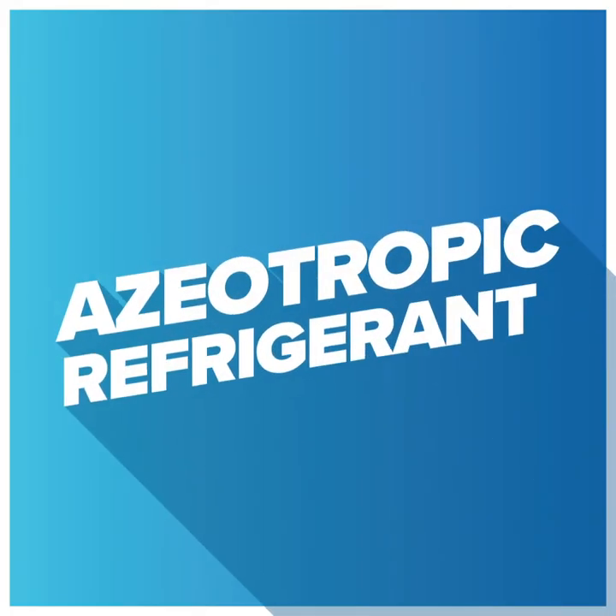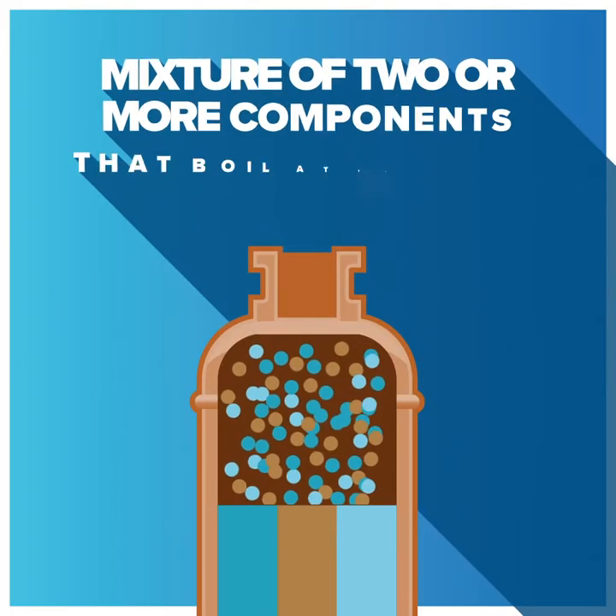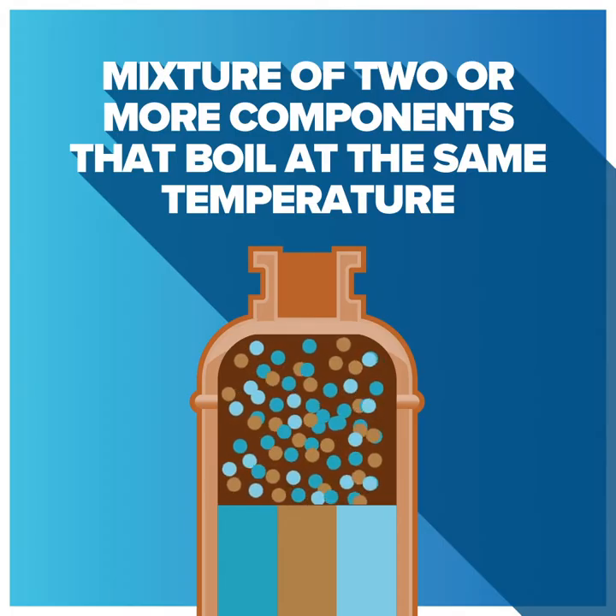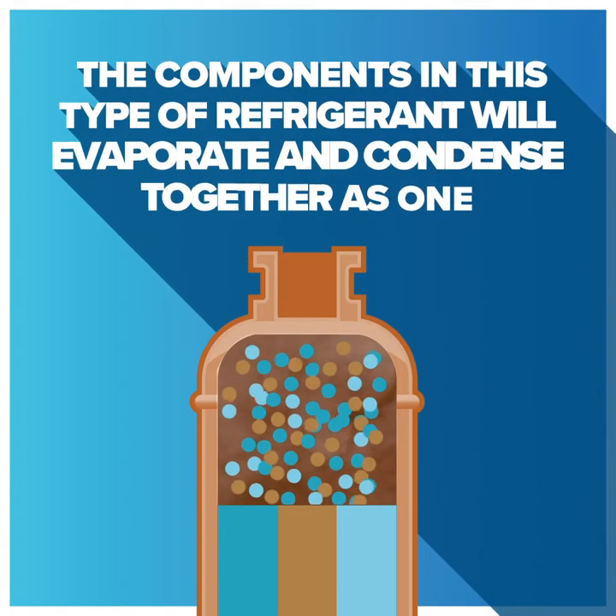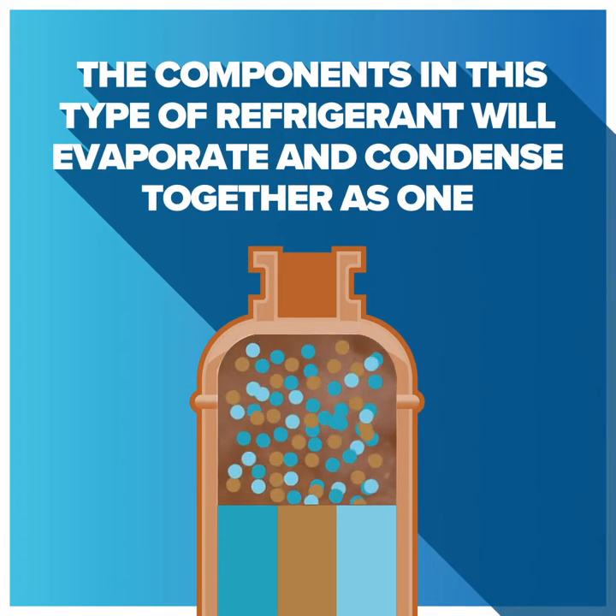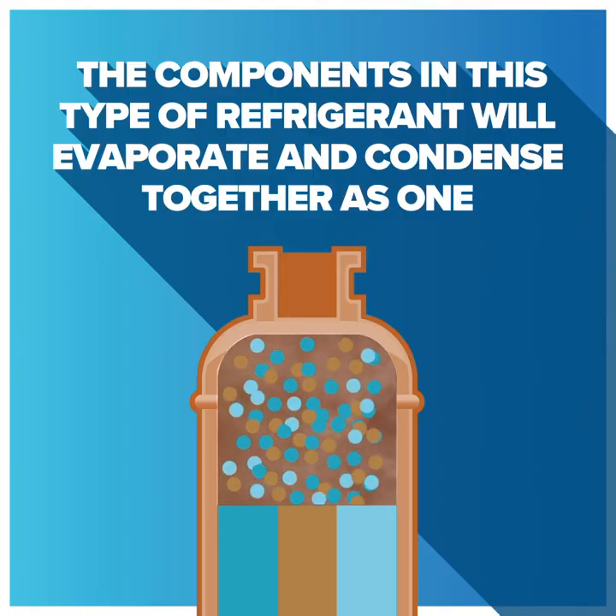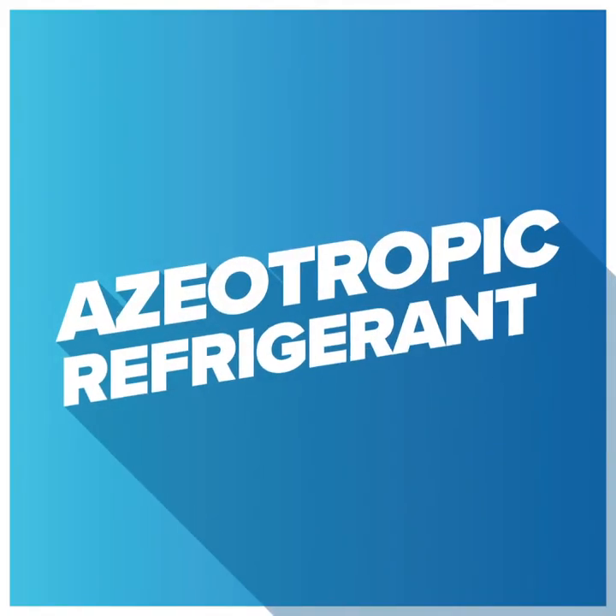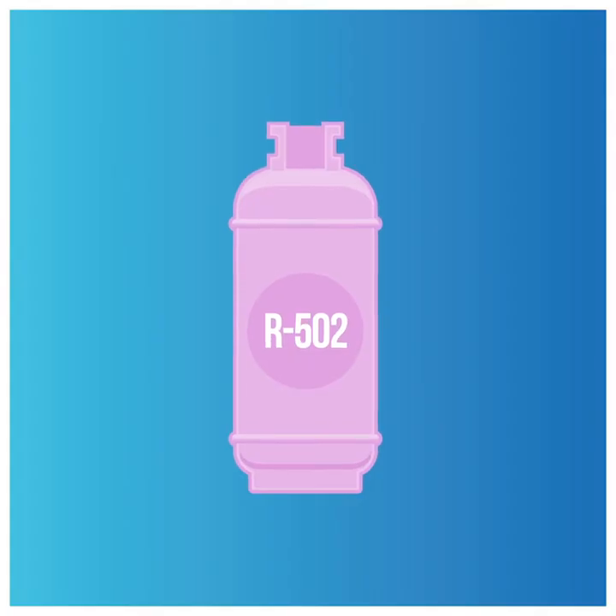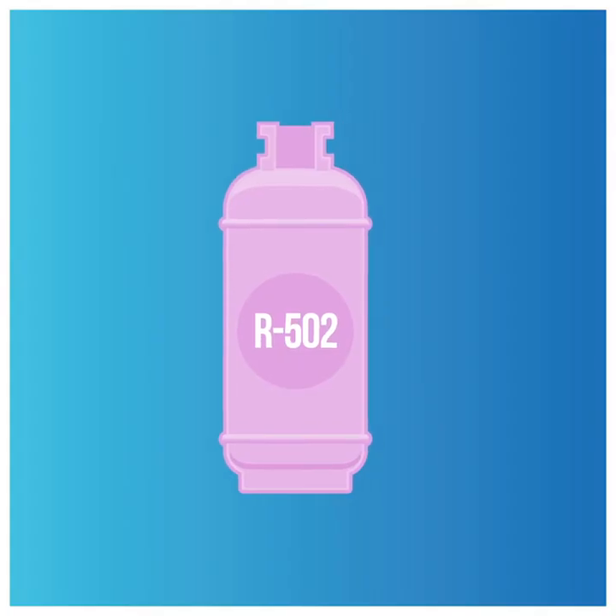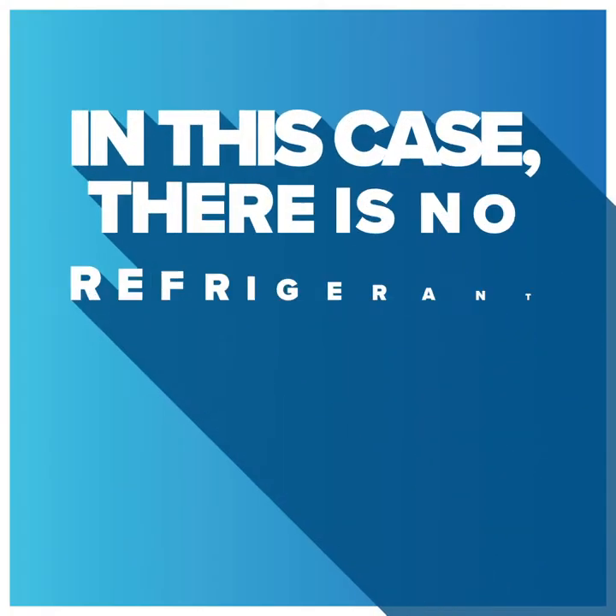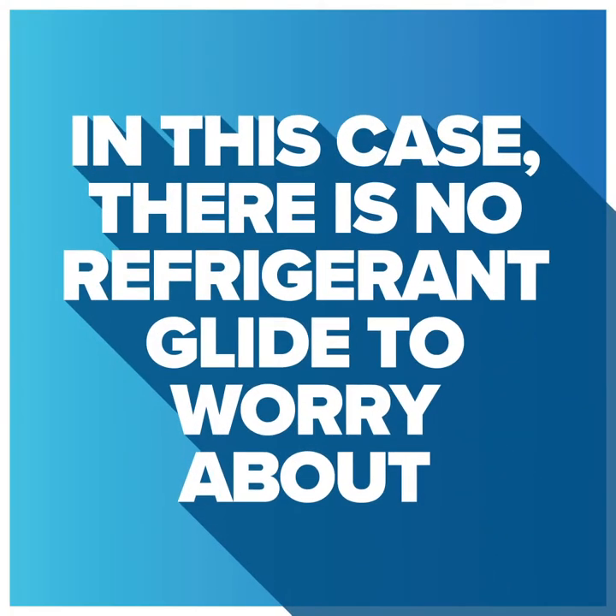An azeotropic refrigerant is a mixture of two or more components that boil at the same temperature. The components in this type of refrigerant will evaporate and condense together as one. An example of an azeotropic refrigerant is R502, which is a blend of R22 and R115. In this case, there is no refrigerant glide to worry about.